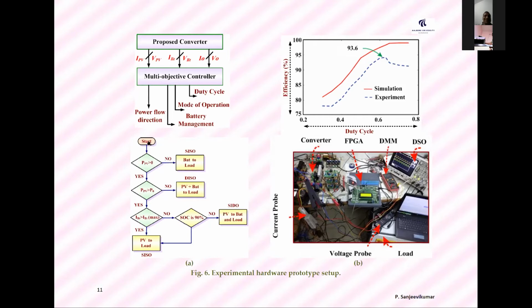The program is started. We check what is the power from the PV. Where it is greater than 0, you go to the next step: check if the power of PV is greater than output power, then go to the next step. Check if battery current is greater than battery max, then go to the last step. PV can connect to the load.